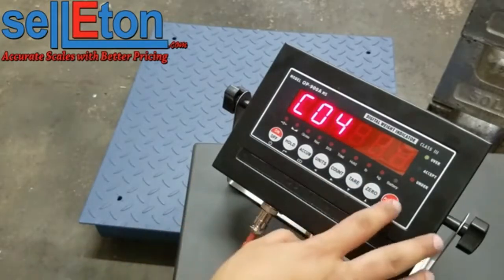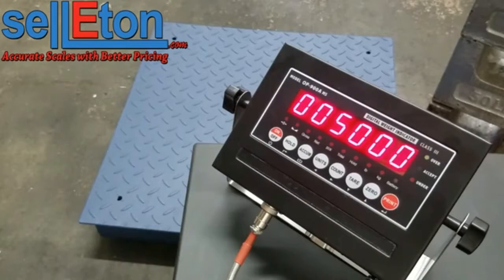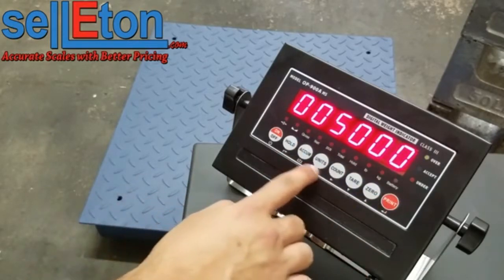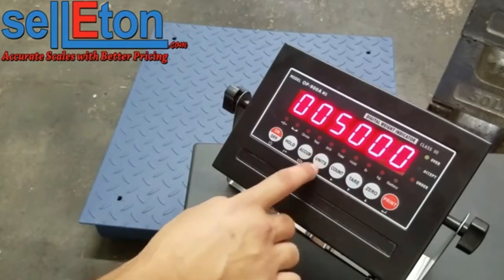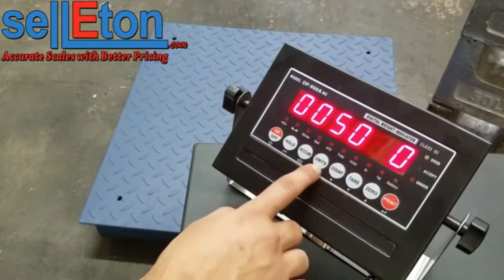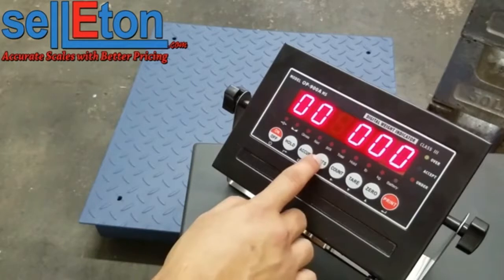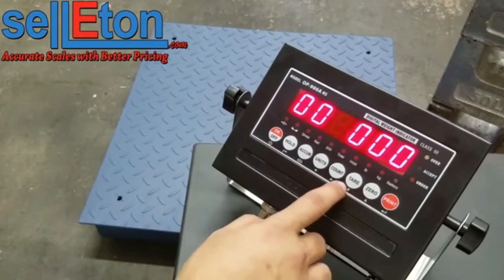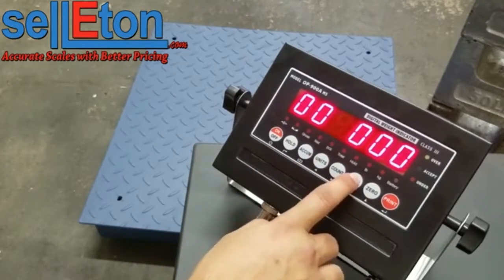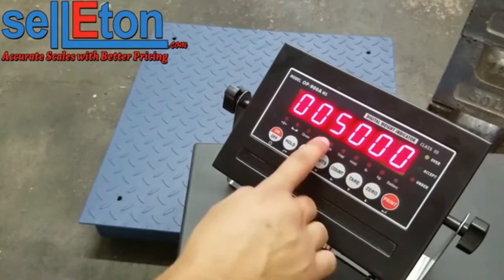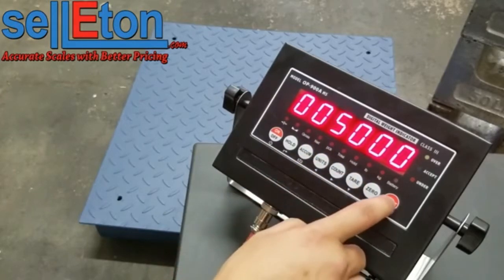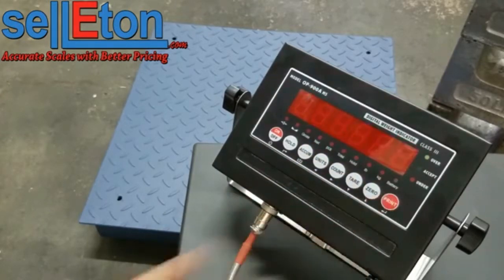C04 is the capacity of the scale. The scale was already pre-calibrated, but if you wanted to change it, you would go back and forth with these two buttons, the units and count, and move them up and down with tare and 0. We're going to leave it at 5,000 pounds here, and press print.